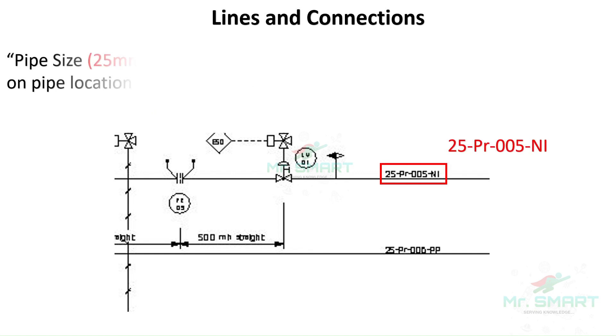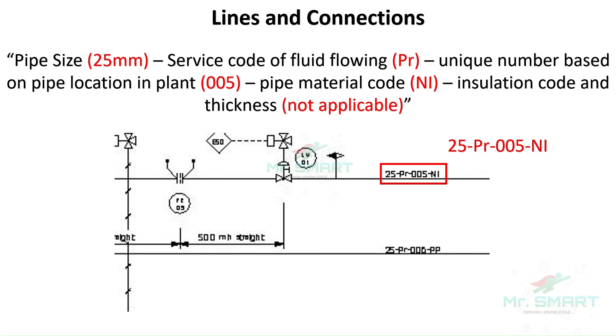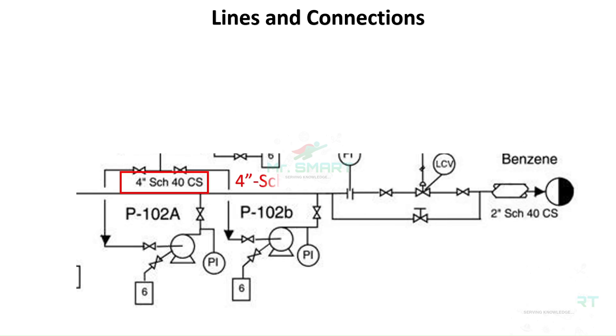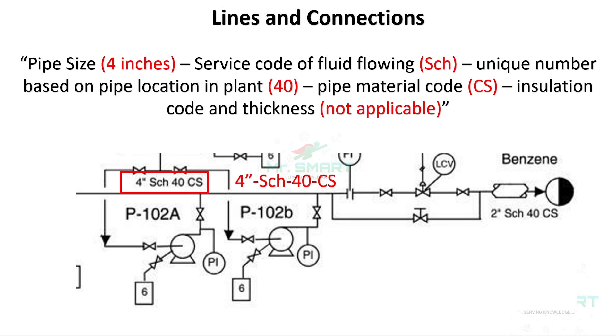You can notice the pipe number in the drawing here as 25PR005NI, which says this pipe size is 25mm, having a fluid with service code Pr flowing inside, a unique plant code of 005, and the material code for the pipe is NI. Insulation is not applicable to this pipe, as the fifth part of the line number is missing. In some drawings, the pipe size will be defined in a different measurement unit system. For example, here in this drawing the pipe size is defined in inches as 4 inches, having a fluid with service code Sch flowing inside, a unique plant code of 40, and the material code for the pipe is CS. Insulation is not applicable to this pipe. Understanding line numbers will give you details about the pipes.